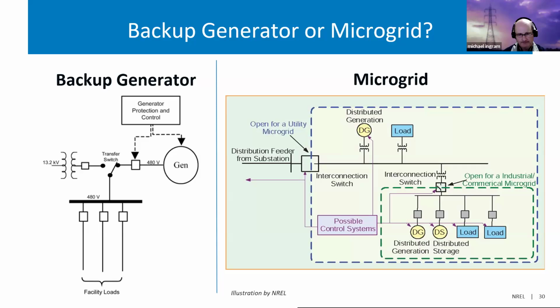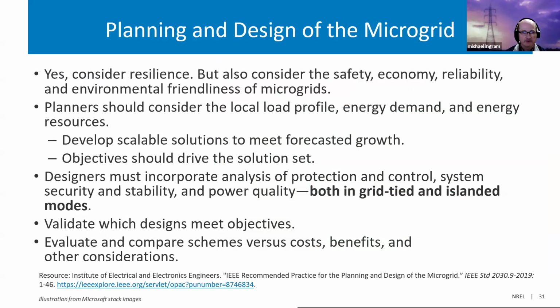Microgrids. My distinction here is to think about whether you need backup generation or whether you need a microgrid. A microgrid is a complex system that requires a lot of maintenance, and in some cases you may just survive with a backup generator. A microgrid can produce energy, put it back onto the grid, but it can, through this device here, isolate and provide energy within that blue box during an outage. But as you can see in that distinction, there's a lot going on. It's a complicated system, and this list begins to tell the story on how to design that microgrid, your considerations.